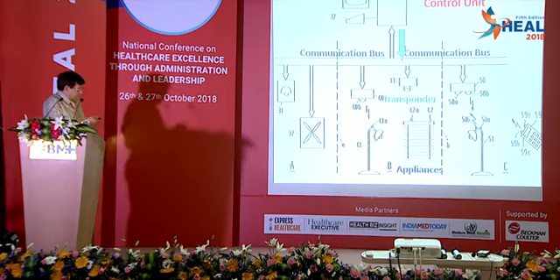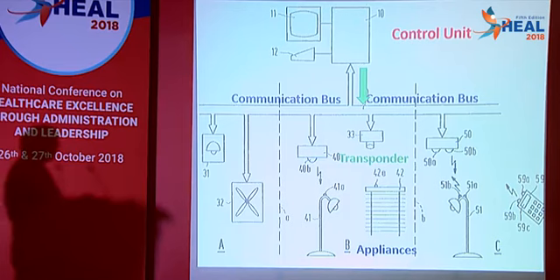Now, same thing in a pictorial form. You have all these devices. You have fans, electrical devices, heating appliances, HVAC system. Then there is a control unit, and there is a communication bus here, and the transponder will allow a two-way communication. Do you want to increase the air pressure, or you do not want to increase the air pressure? You have a two-way communication where the pressure is less, where it is low, and while sitting on the control unit, you are doing that. That is the integrated building management system.